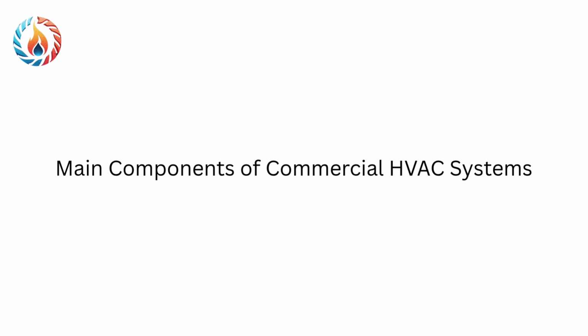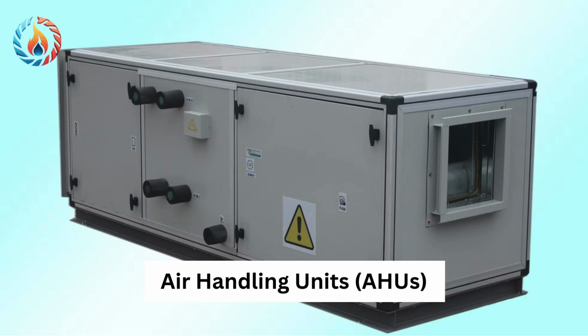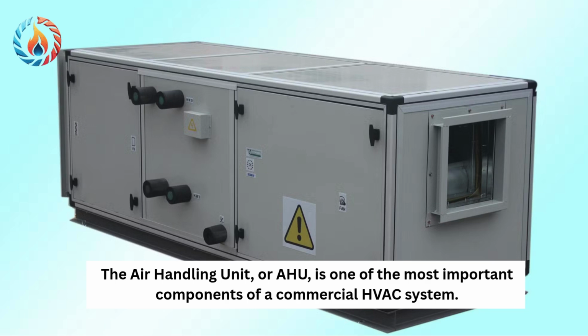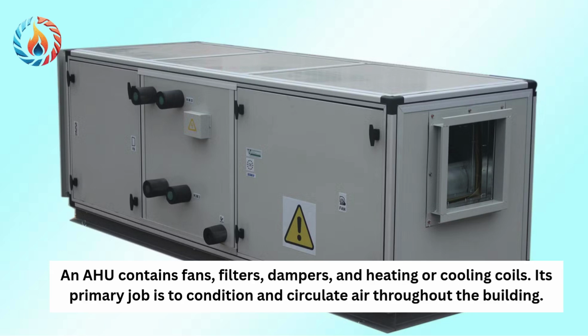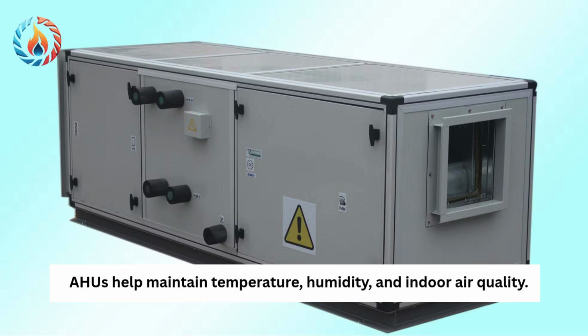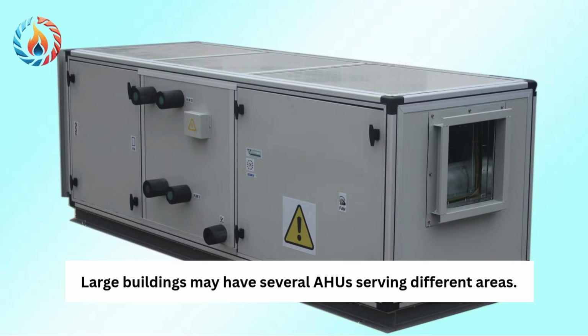Main components of commercial HVAC systems. Air handling units, AHUs. The air handling unit or AHU is one of the most important components of a commercial HVAC system. An AHU contains fans, filters, dampers, and heating or cooling coils. Its primary job is to condition and circulate air throughout the building. AHUs help maintain temperature, humidity, and indoor air quality. Large buildings may have several AHUs serving different areas.